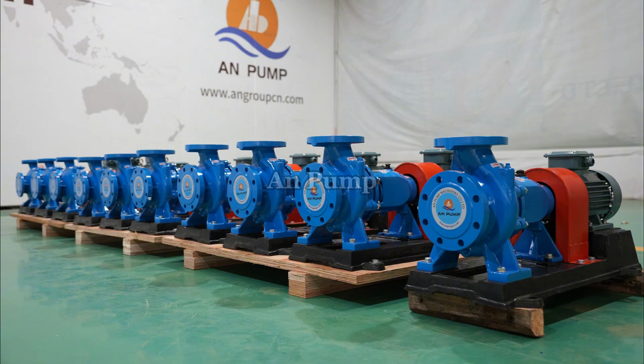So to wrap up, centrifugal pumps are everywhere in our industrial, municipal, and commercial infrastructure. Understanding the differences between end-suction, split-case, multistage, slurry, and submersible designs is the foundation of good pump selection. The wrong pump for your application will fail early, waste energy, and cause unplanned downtime. The right pump, properly sized and specified, can give you decades of reliable service. For any complex or high-stakes application, always consult a qualified rotating equipment engineer or work directly with a pump manufacturer's application engineering team. Review the pump datasheets, performance curves, and dimensional drawings against your actual system hydraulic model before you issue a final specification.